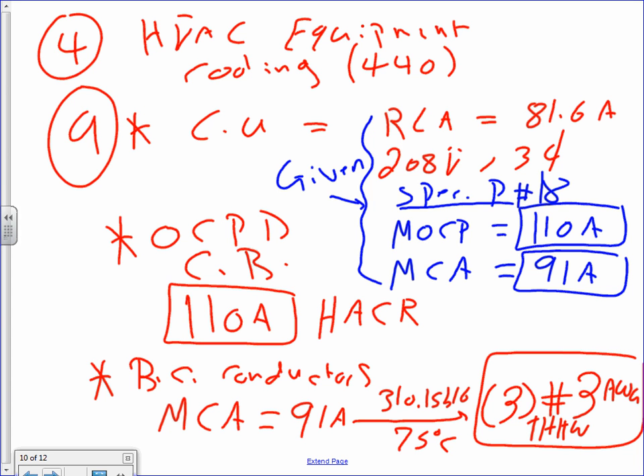The cooling unit's rated load amps on the nameplate is 81.6 amps. The voltage is 208 volt 3-phase. And all this information is from spec page number 18, I believe. That's a spec that I gave you guys. I hope the page from last quarter didn't change. Can anybody verify the spec, guys? Is this number 18 for this year?